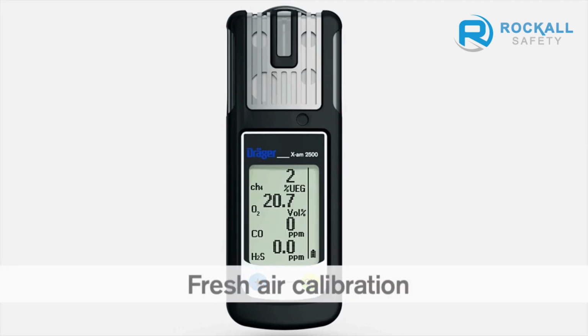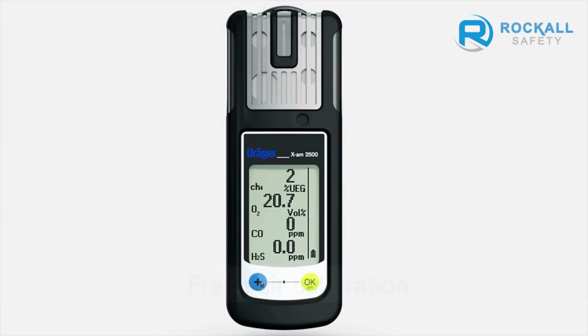Fresh air calibration sets the oxygen channel to 20.9% by volume and the sensors to 0. Make sure you are in an area of clean air during fresh air calibration.